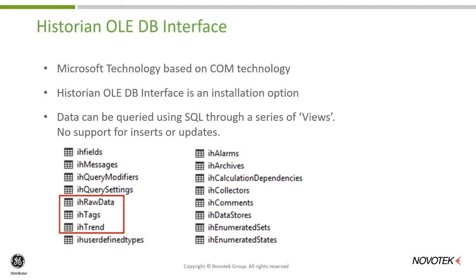Let's look at the historian OLEDB interface in more detail. It's based on Microsoft technology. The original concept was that it would replace ODBC interfaces, though probably that's not the case anymore. You need to select it during the historian archiver installation routine. It allows data to be queried through SQL, and although we talk about it being time series, the data manifests itself as a series of views — you can query the views, but there's no support for inserts or updates.